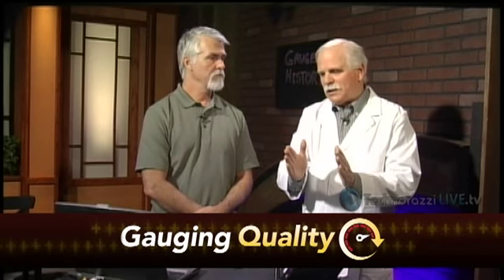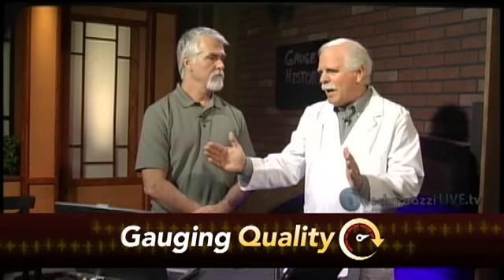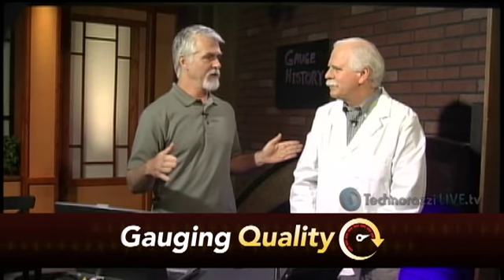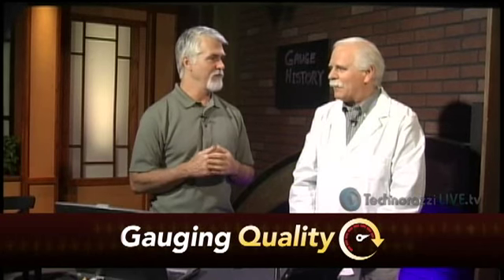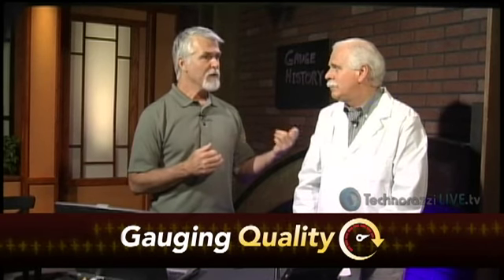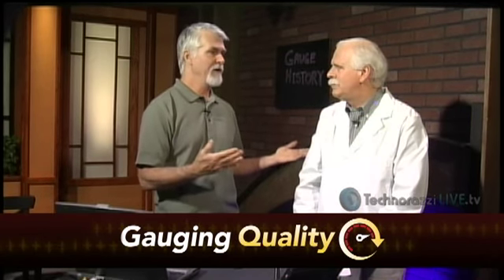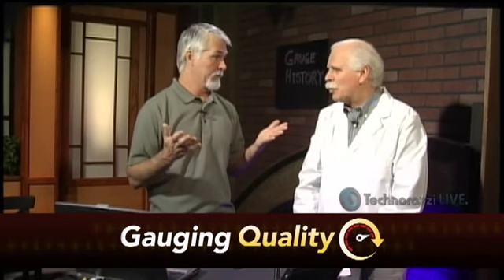The only problem with extending it out like that is that each time it gets longer and longer. When it finally fails, you're going to be way out on the interval. It's kind of a coin toss. You may at some point extend it out and go over, and you don't know it until it comes back in for calibration. Then you realize you've been out 2 years. Too long, yeah, exactly. And the only time you know for sure that gauge was in tolerance was the last time it was calibrated. Right, but I would imagine that if no calibration was required, your trend would basically be a straight line. It would be, if everything was linear.